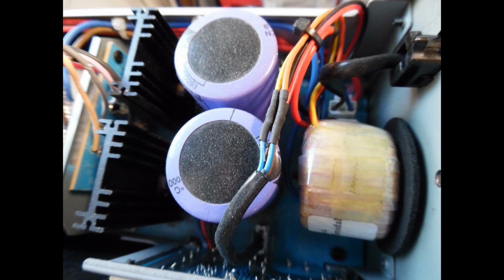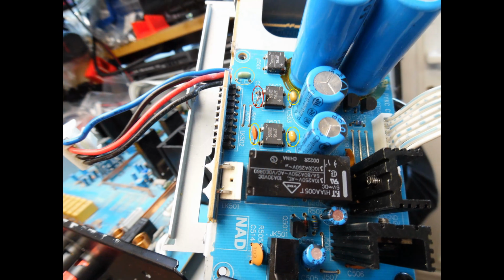On there you'll see multiple protection fuses, and a vertical board mounted with the standby relay. I've circled where you can see these 100 nanofarad, 100 volt rated high frequency capacitors, and one circled in red is the one which has gone short circuit.